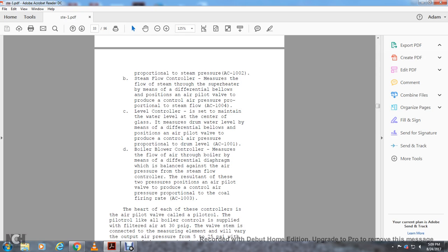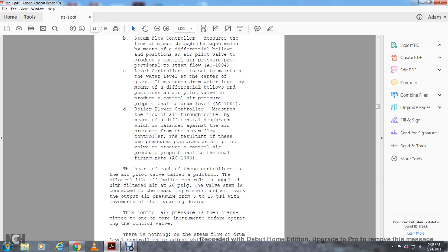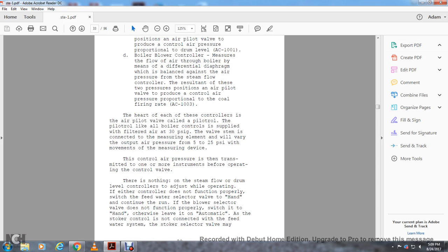Boiler blower control measures the flow of the air through the boiler with the differential diaphragm balanced against the air with the pressure of the steam flow control. The resultant of the two pressures positions the air pilot valve to produce the control air pressure proportional to the firing rate, AC 1003.